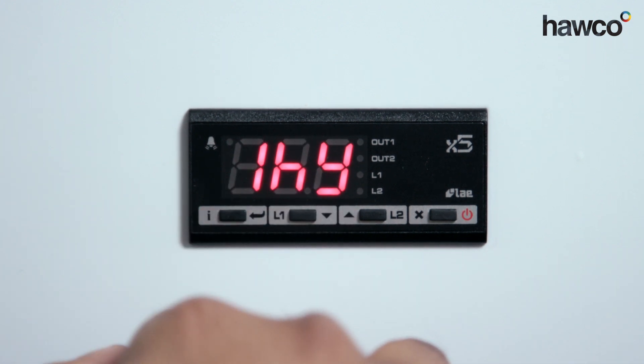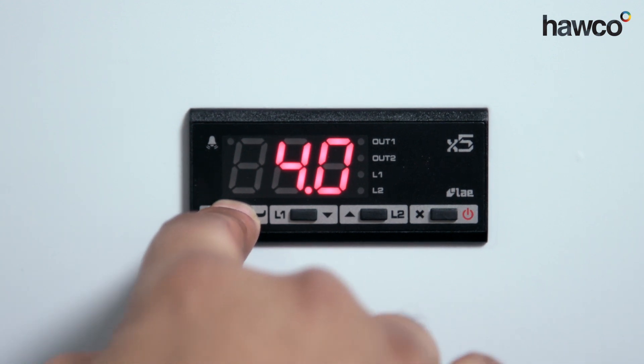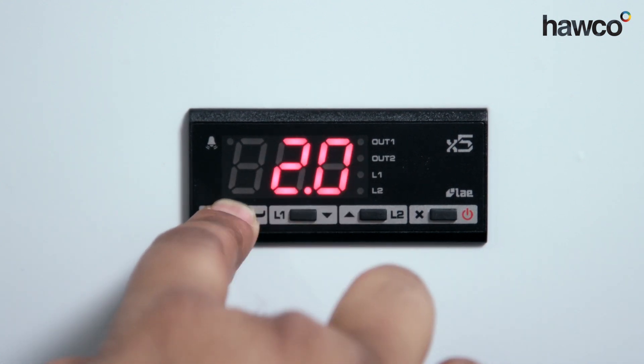The next one we're going to come across is 1HY. This is our differential. So by setting it at four degrees, when we get to four degrees above set point, the refrigerator will turn on. So I'm going to reduce this down to two. There's a differential of two degrees for the refrigerator.